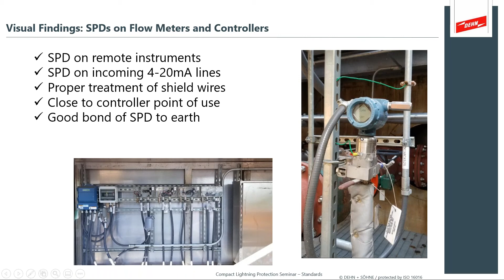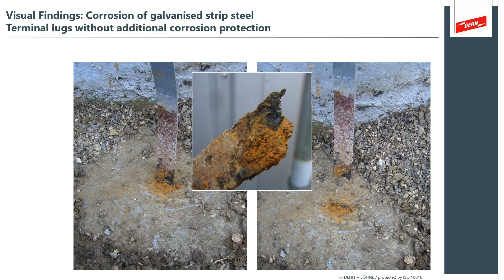Visual findings, other types of things that go wrong: corrosion of galvanized materials. Remember we talked about where the conductor emerges from the soil as a point of protection. Well, over time, this one corroded to the point where when we hit it with the stick, it broke loose. And that's a major problem. That could have been a transformer bond, and you don't know now that the transformer could be floating. That could be a really big electrical problem. So these are the types of things that just go wrong over time. It's just maintenance and wear and tear over time.